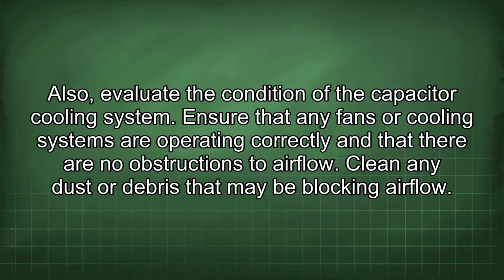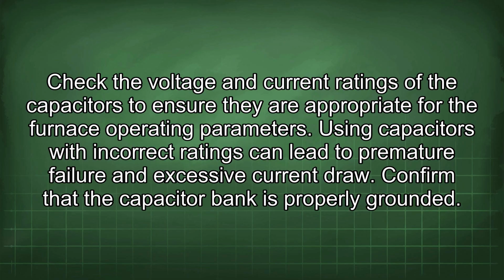Ensure that any fans or cooling systems are operating correctly and that there are no obstructions to airflow. Clean any dust or debris that may be blocking airflow. Check the voltage and current ratings of the capacitors to ensure they are appropriate for the furnace operating parameters. Using capacitors with incorrect ratings can lead to premature failure and excessive current draw.